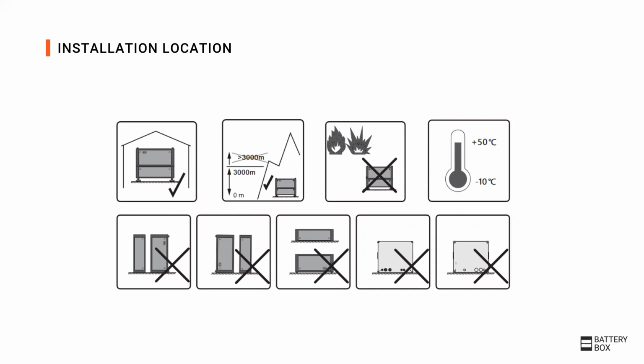Here you see the requirements for the installation location. The temperature range is from -10 degrees to +50 degrees. The battery can operate within this temperature range, however the power will be limited below 5 degrees. The battery should not be placed close to easily inflammable materials. The battery box has a protection rating of IP20 and should be placed inside to protect the battery against weather conditions. The battery should not be placed on the side, but always in the correct direction.